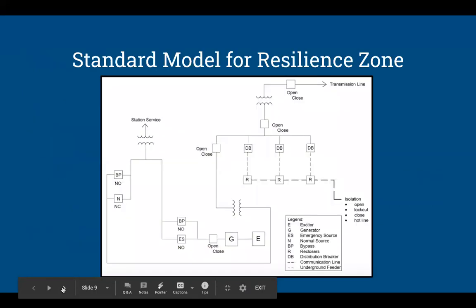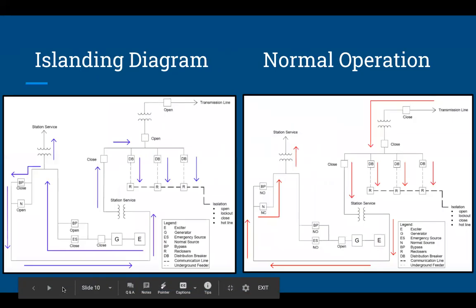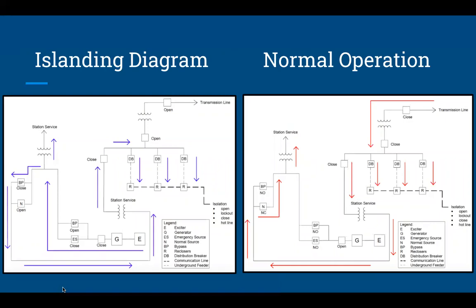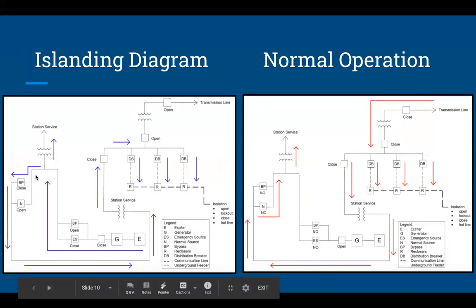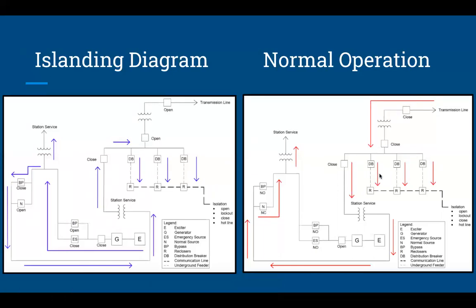From the simulation, we've been able to create a standard model for resilience zones. And through this standard model, we were able to create a diagram for both islanding and normal operation. In our islanding diagram, we see that our isolated distribution lines are being fed from the emergency generator, whereas in normal operation, they're being fed through the overhead transmission lines and out through our distribution. That pretty much wraps up our project. Hope you enjoyed it.